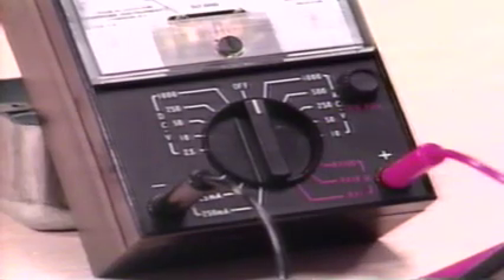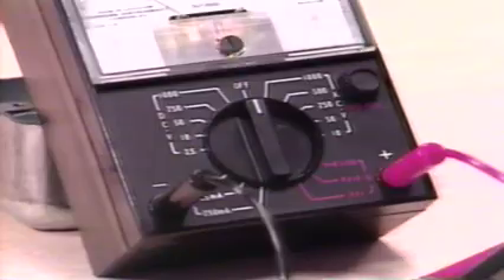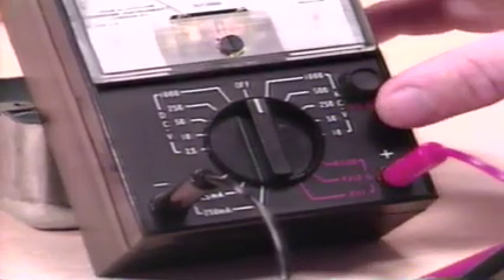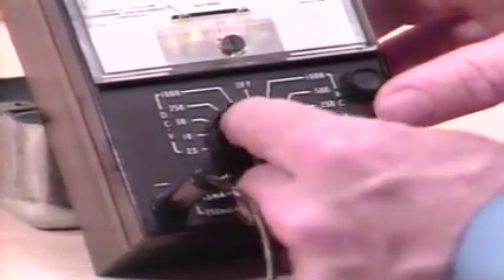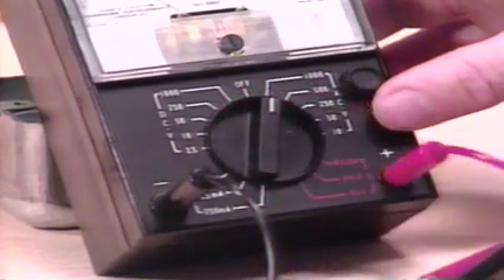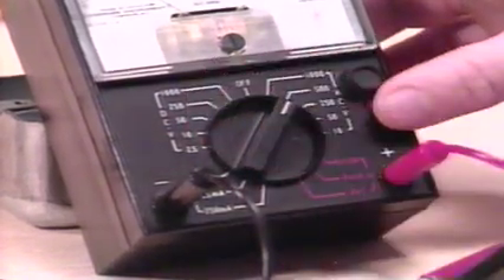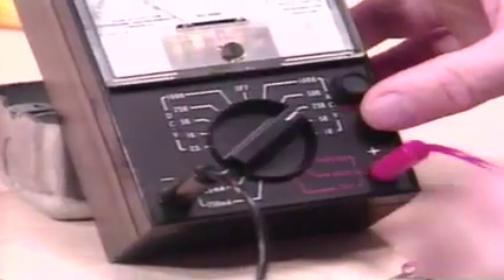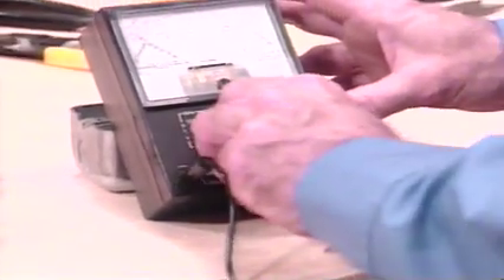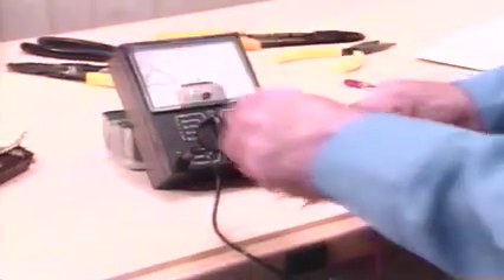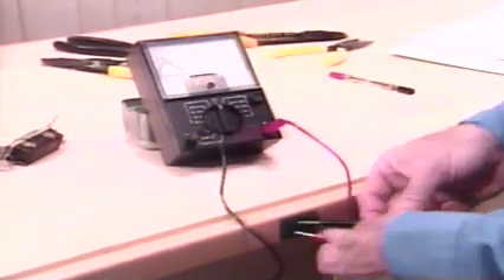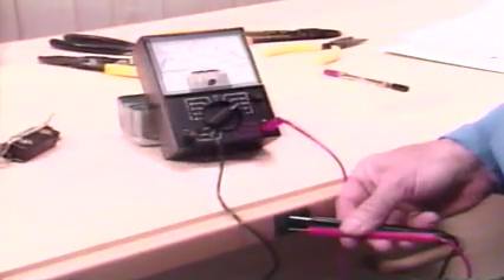When taking a volt AC measurement and the value of the voltage to be measured is unknown, always start with the highest range of the meter and progressively go lower until an appropriate reading is obtained. In other words, if you're measuring the voltage at this electrical outlet, begin with the switch at the highest setting. By taking a measurement, you read 110 volts AC here. If the switch setting had been lower, you potentially could damage your meter.